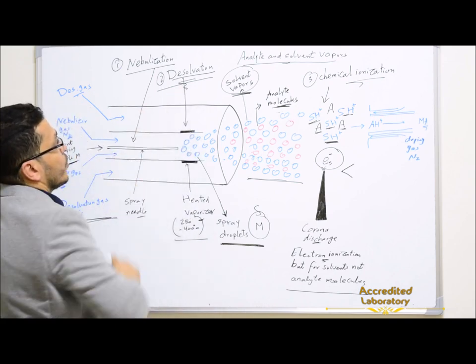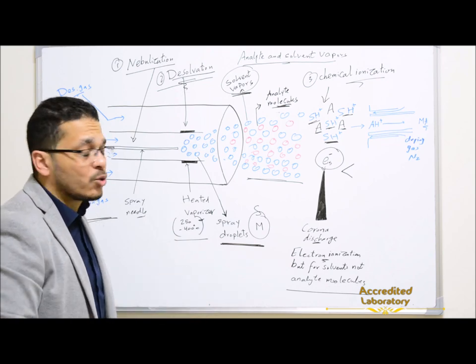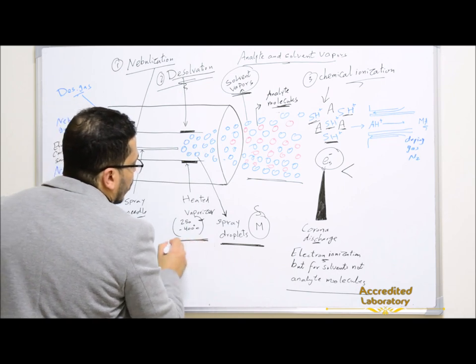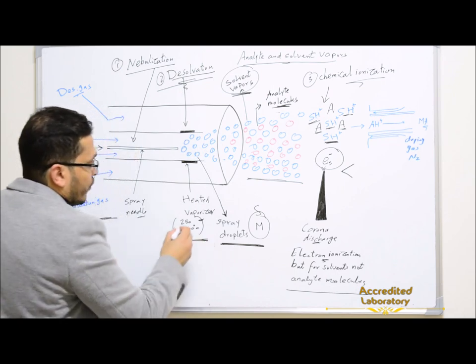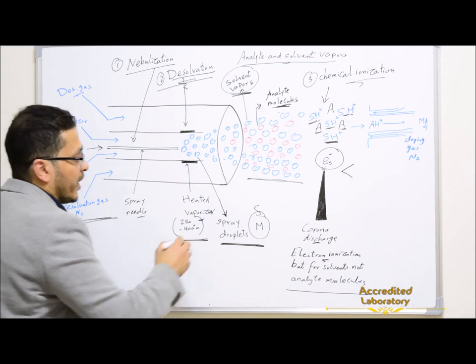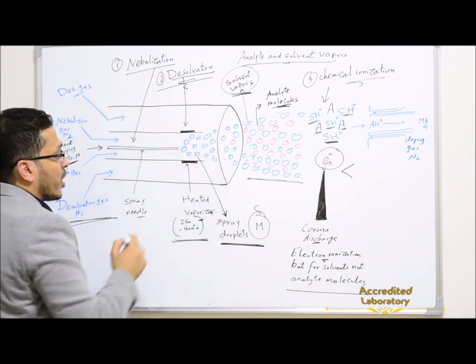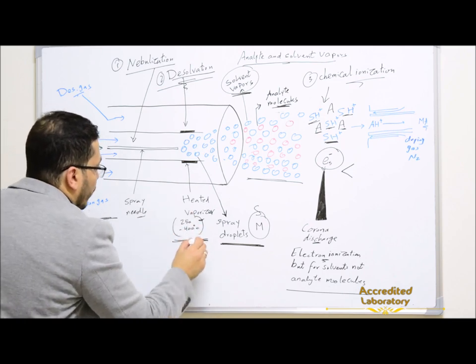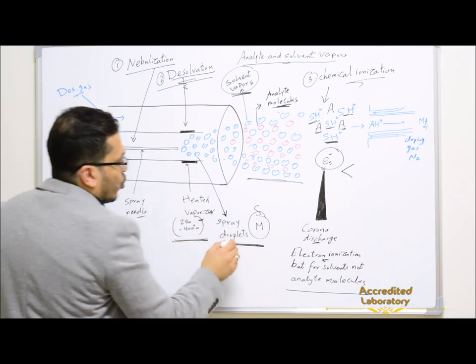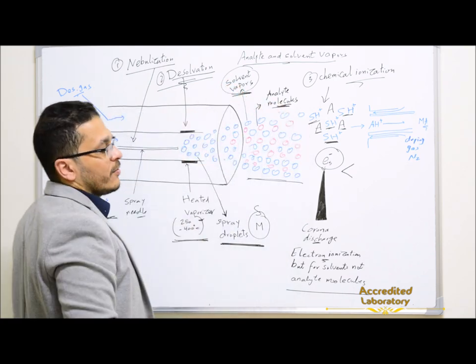Then after that, the desolvation process removes or evaporates the solvent molecules by the effect of a heated vaporizer at 250 up to 400 degrees centigrade. These spray droplets move through that heated vaporizer, and by the effect of the heater and desolvation gas, these spray droplets will be converted to analyte molecules and solvent vapors.